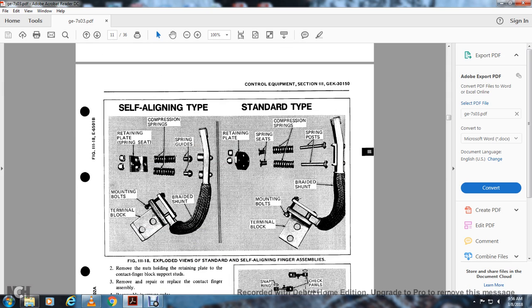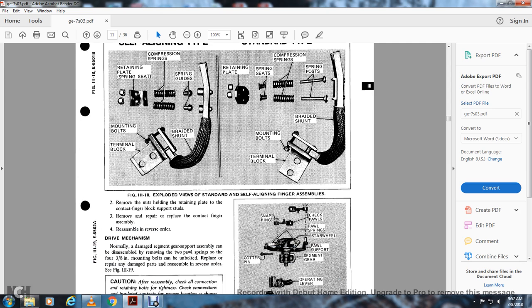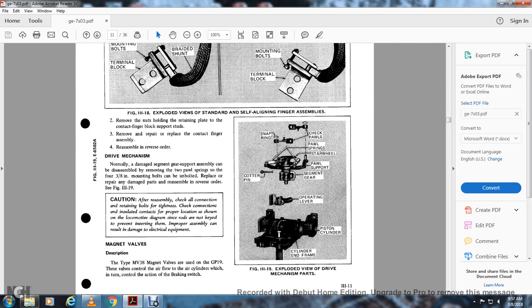Figure 318, exploded view of the standard self-aligning finger assemblies: terminal block mounting bolts, braided shunt, spring guides, compression springs, and retaining spring seat with the self-aligned type. Standard type: retaining plate, spring seat, compression spring, spring post, braided shunt, mounting bolts, and terminal block. Two, remove the nut holding the retaining plate with the contact finger block support studs. So, remove the plate with the contact finger assembly. Replace it. Reassemble in reverse order.